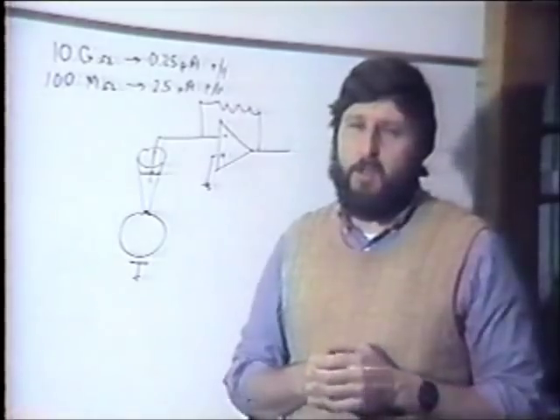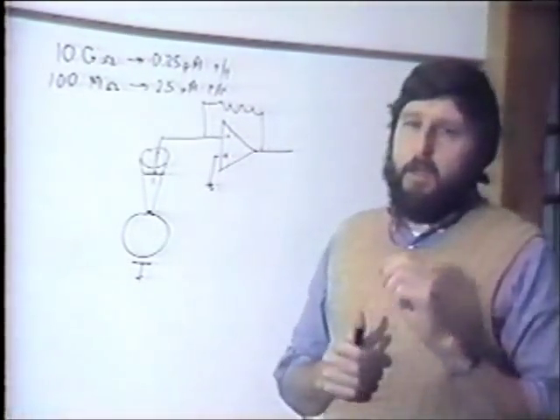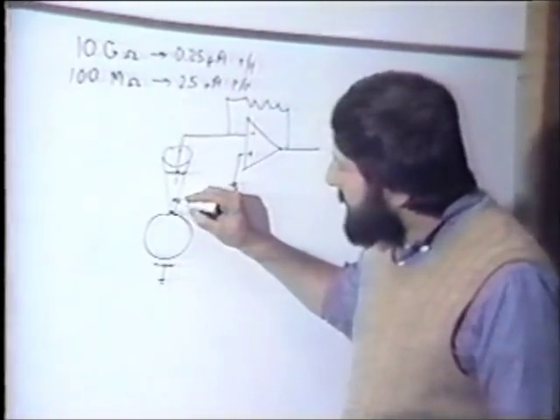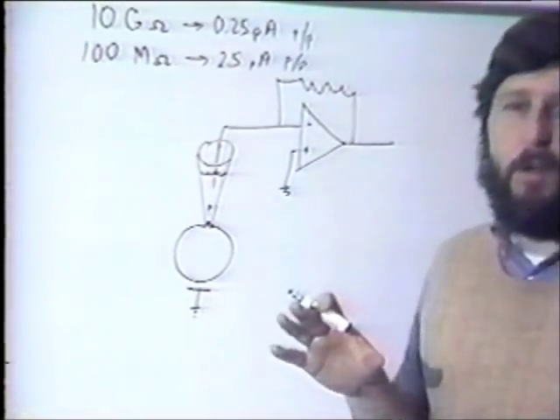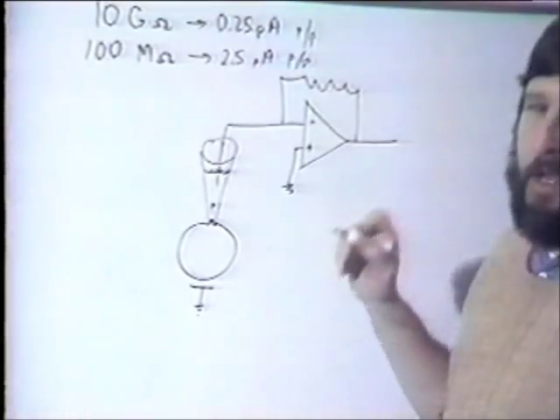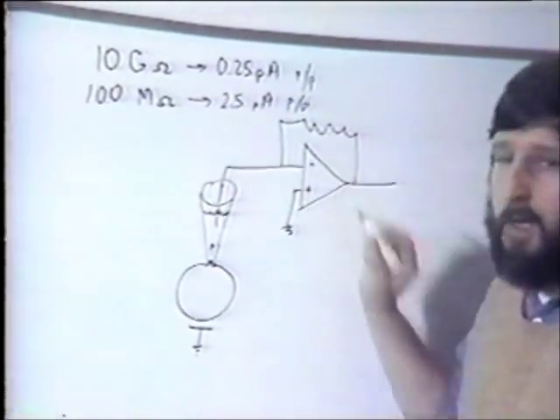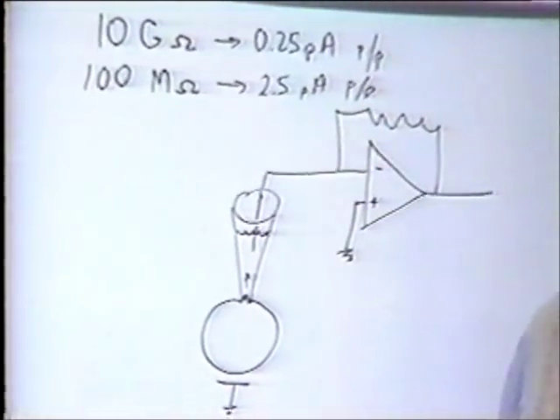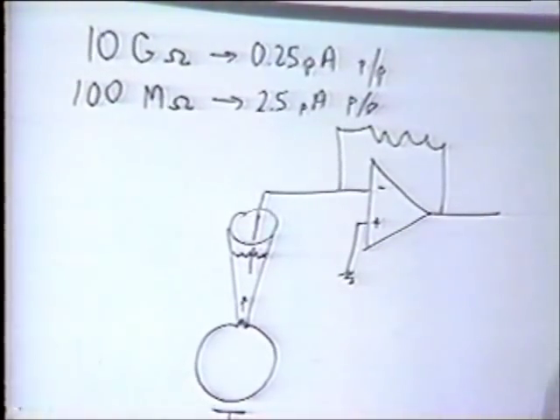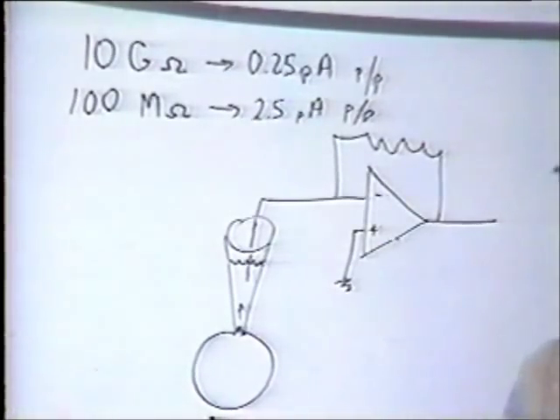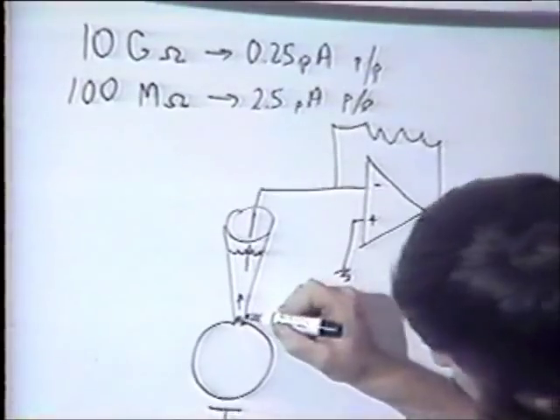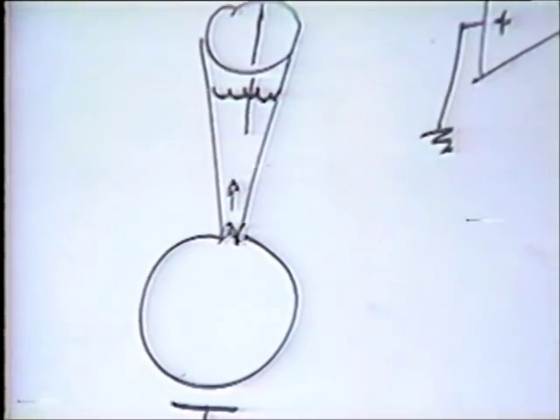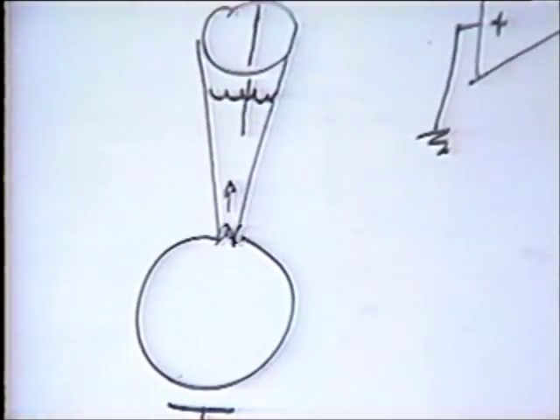How do you record single channels? The basic principle is to apply an electrode to the cell surface that will collect the current and amplify it with a current-to-voltage converter. The current-to-voltage converter keeps the electrode basically at ground potential. The standard current-to-voltage converter uses a high resistance feedback element — 10 gig-ohms to 50 gig-ohms. The key to making the single-channel measurement work is getting a tight seal between the membrane and this pipette. That resistance has to be, at minimum, one gig-ohm, and preferably much higher.